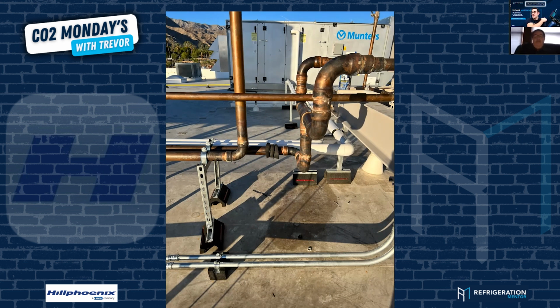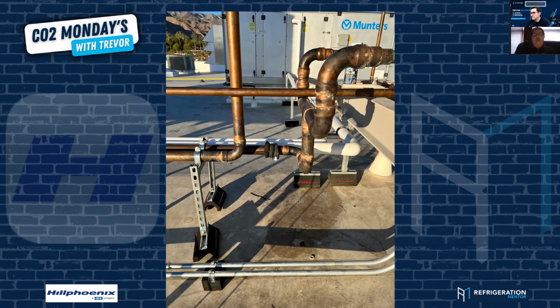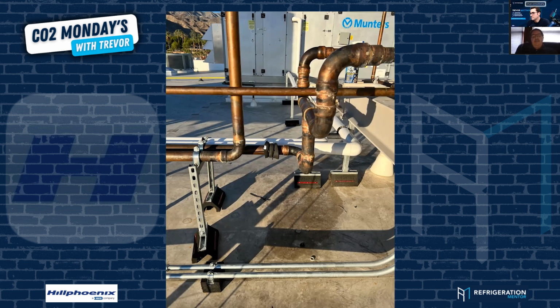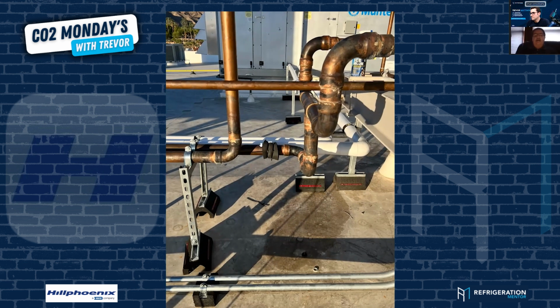Yeah, exactly. All right, so this would be, I'm almost guessing a BAC by the piping, but this is a drop leg into a bullhead, which is good. But the problem is they've landed the drop leg temp sensors down here on the common. It will never work like that. If you have liquid all the time, you'll be okay. But if the rack ever goes transcritical, the temperature difference between the 6 to 12 inch header leaving the rack and there is going to be significant enough to affect the algorithm, and you're going to run off on high pressure. It actually makes it think there are non-condensables in there.